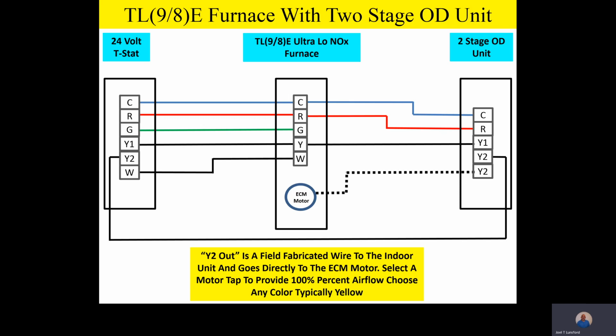So for a Y2 call, you're going to have a terminal outside that says Y2 out. That Y2 out will be a field fabricated wire. We're going to come in and land it on the ECM motor to give us 100% airflow. And so that 100% airflow will come on whenever we have a Y2 output from the outdoor unit. And so really what we're doing, team, we're letting our champion outdoor two-stage unit command second stage airflow inside when it's in second stage cooling.